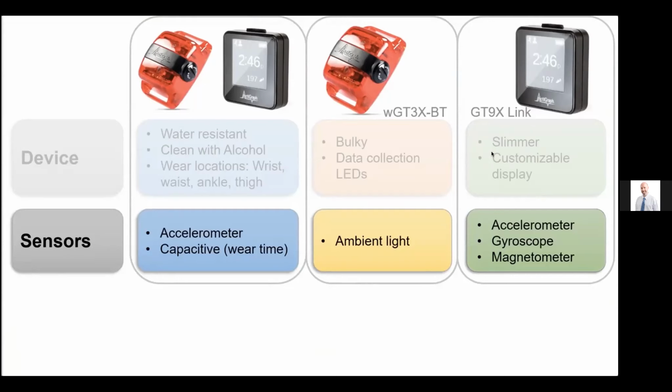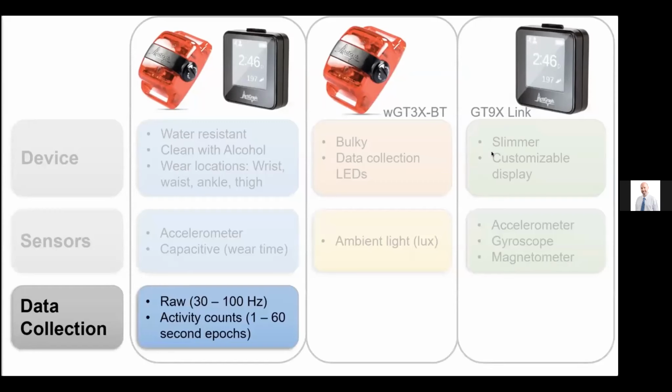What is often helpful for many research studies is the inertial measurement unit, or IMU, that is in the Link device and consists of an accelerometer, gyroscope, and magnetometer. The IMU provides raw position and rotation data, but is not able to communicate with other IMUs to be able to provide kinematic data. Using the IMU substantially decreases the battery life of the device. However, the IMU is in addition to a separate accelerometer, so it can be turned off to conserve battery when you only need to collect accelerometer data.